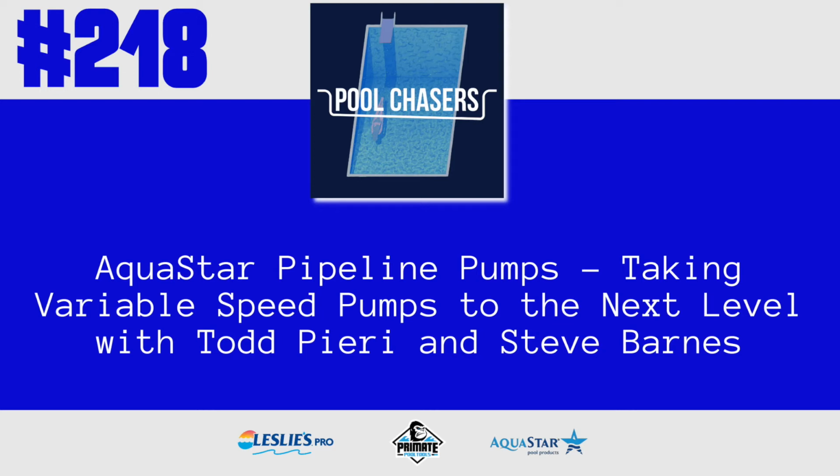So a volute pump is if you take a pipe, whatever size, 2.5 inch, and heat bend it and wrap it around an impeller, so it's smaller and then it gets bigger. That's the most efficient way. Water coming out of the spinning impeller collects all the way around and then leaves the pump. But that is real annoying to install, because now everything's offset. They don't look great in a residential environment, because people just aren't accustomed to it. The engineers were like, let's chase performance and energy efficiency.